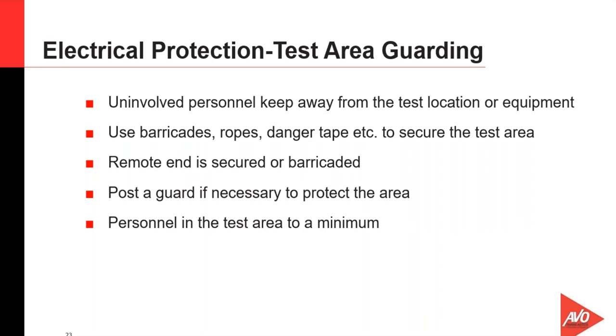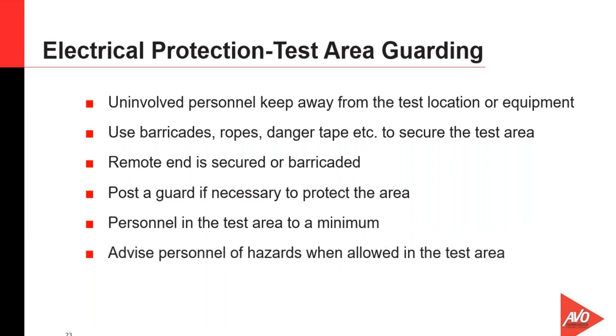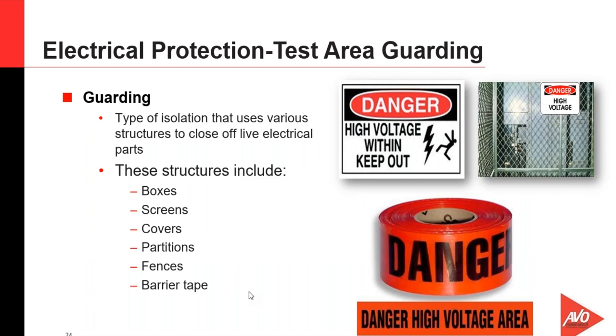Keep personnel in the test area to a minimum. Only those who are necessary for operation of the equipment and for safety are necessary to be in the test area as we're testing. If we have other personnel in the test area during a set of testing, we need to make sure that everyone understands the hazards, the voltage levels we're testing at, and the issues, the approach distances and things like that to the parts that we're actually going to have energized. Here's some more examples of guarding, and we can have different types of things.